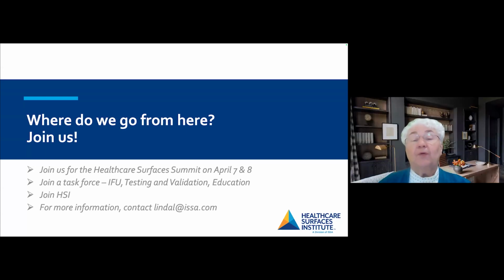I want to address the question that someone asked about what a facility is to do when the answer is no to many of the questions about how do I clean it, et cetera, because we really need to have the device. So you really have to do a risk assessment. You have to also work with the manufacturer. Could they do additional testing?